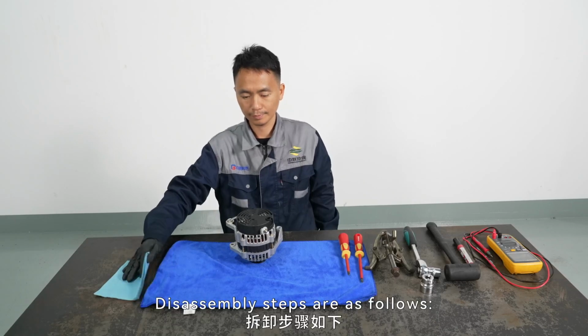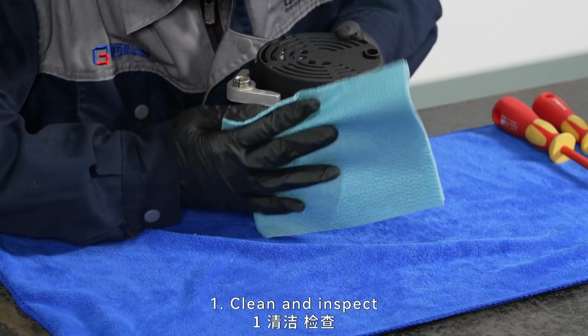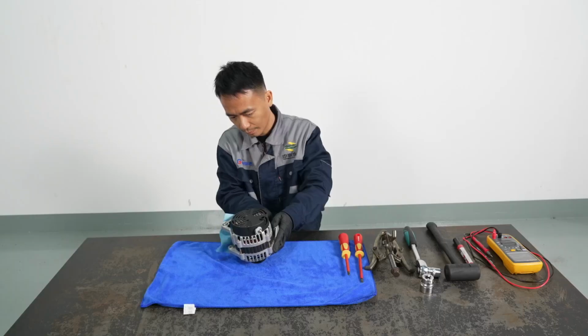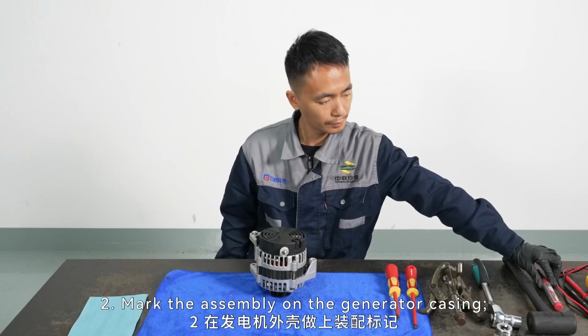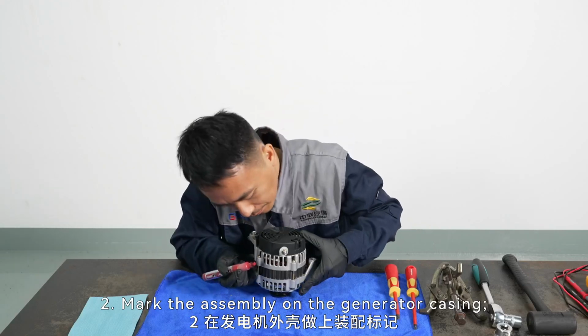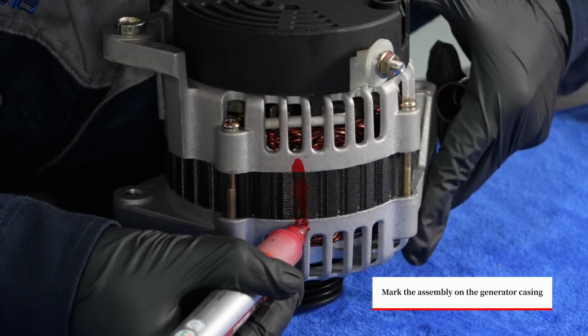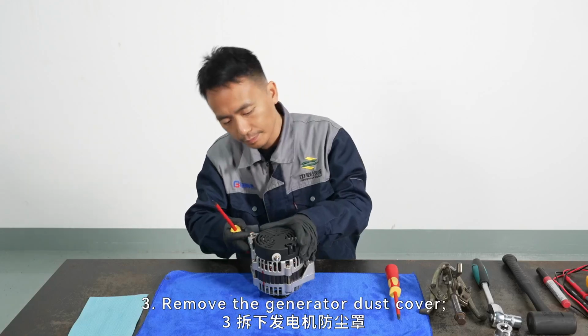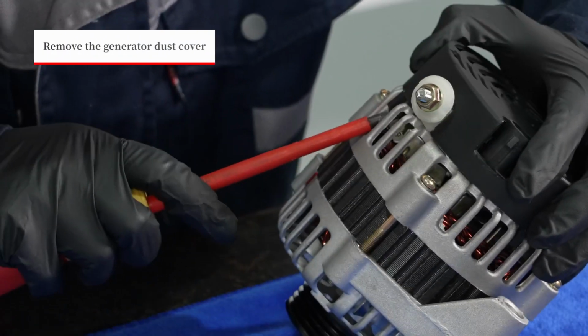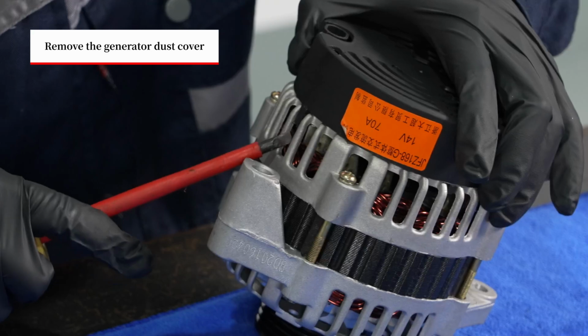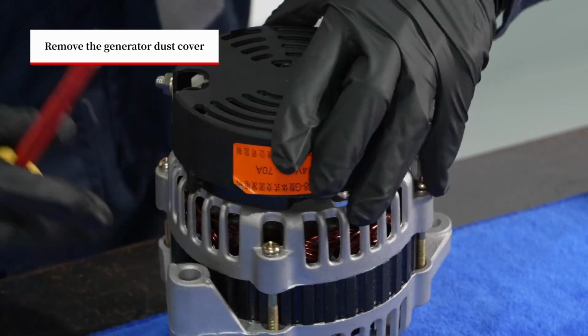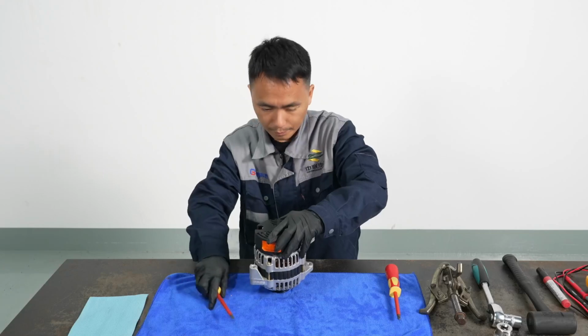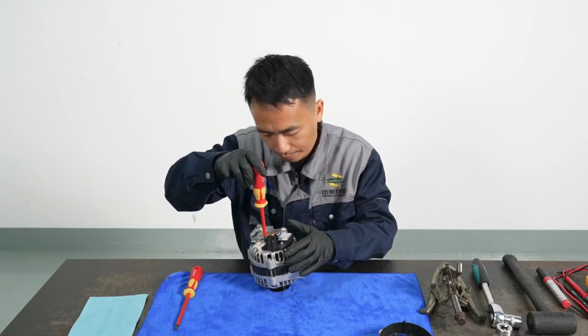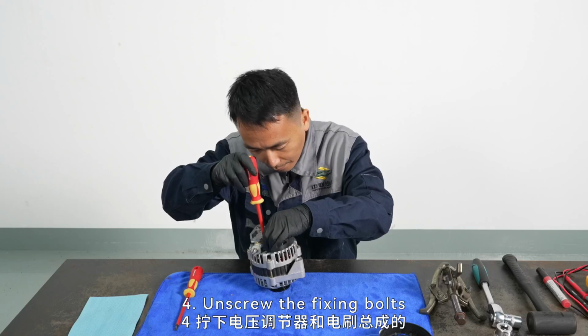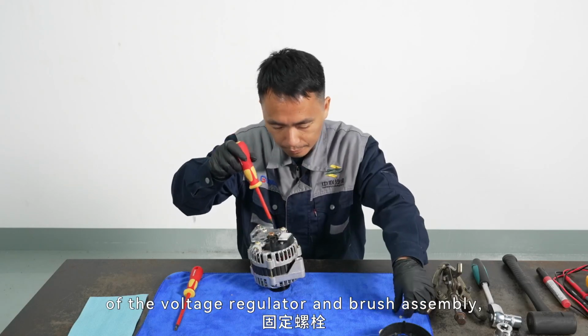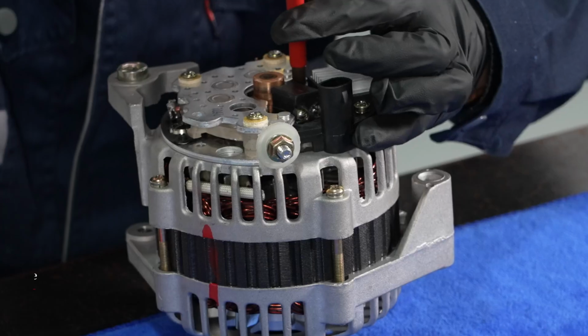Disassembly steps are as follows. 1. Clean and inspect the generator surface for damage. 2. Mark the assembly on the generator casing. 3. Remove the generator dust cover. 4. Unscrew the fixing bolts of the voltage regulator and brush assembly, then remove them.